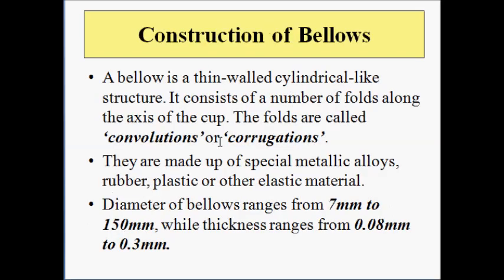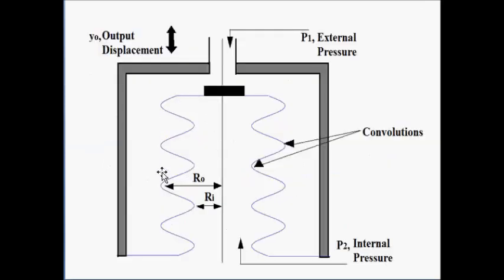Now the construction of the bellow. A bellow is generally a thin-walled cylindrical cup-shaped structure which has a number of folds or convolutions or corrugations along the axis. This cylindrical structure can be made of metallic alloy, rubber, plastic or any other elastic material which can be stretched or compressed without breaking. Generally the bellows is in this form.